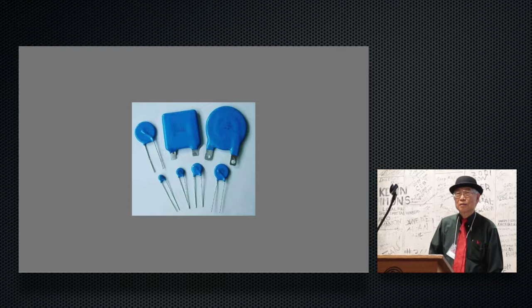Another device with better performance but more expensive is a line conditioner. It works very differently than surge protectors. Instead of clamping the circuit, it isolates it, blocking the pulse from getting to the secondary side. It needs a very special transformer, and they're quite expensive, although you can get one on eBay. Just be careful of the shipping, because they're quite heavy.